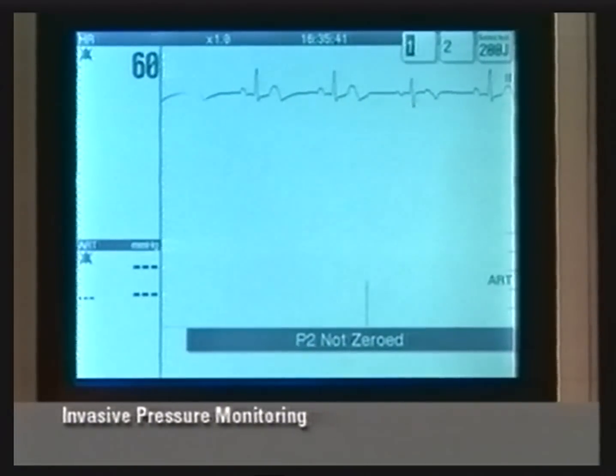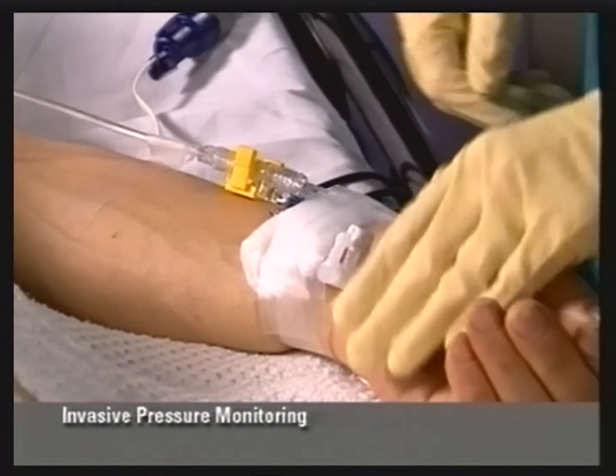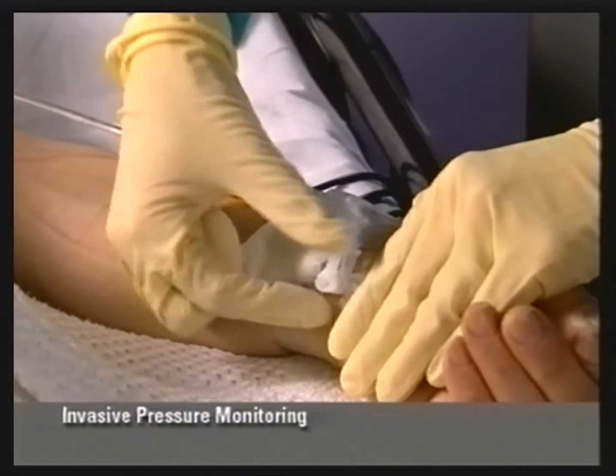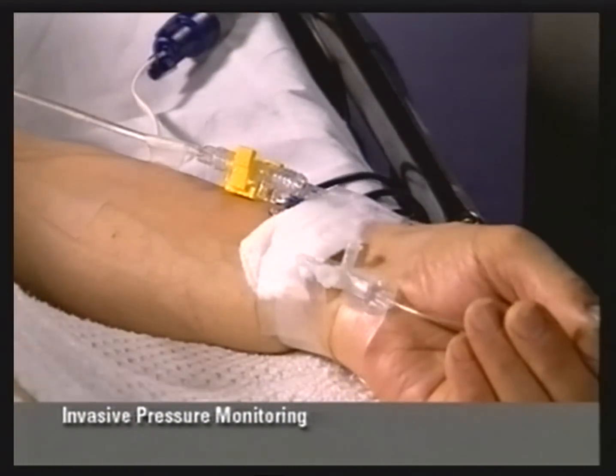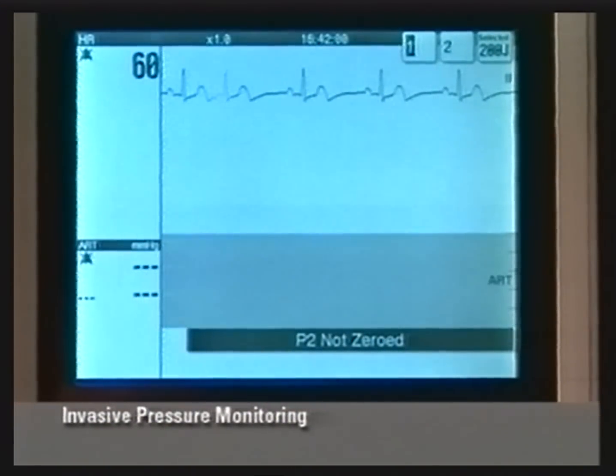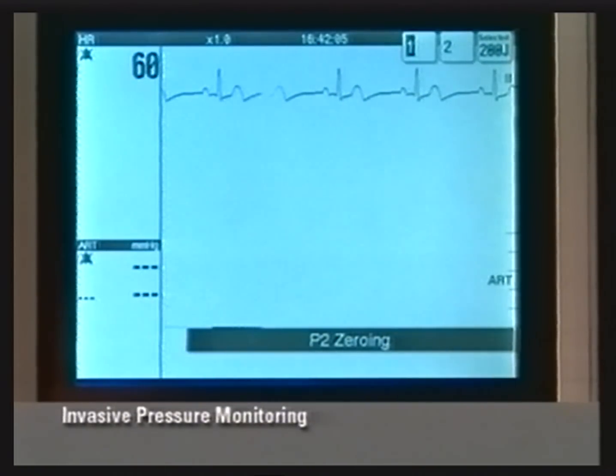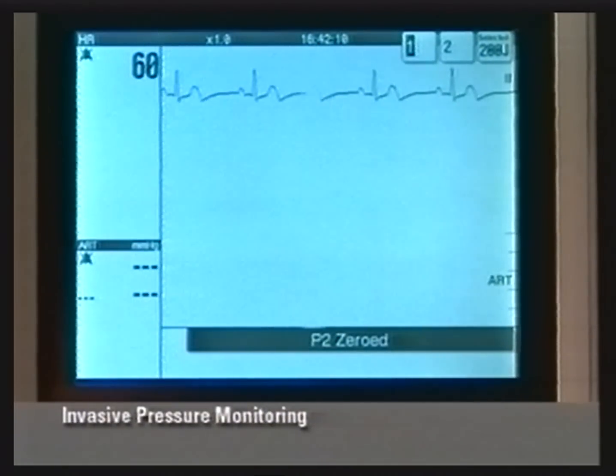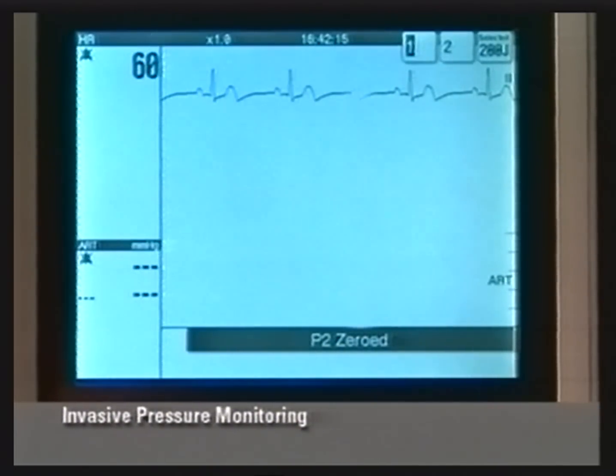Notice that the message P2 not zeroed is displayed in the status area. To avoid offset errors, a zero reference must be established before a meaningful pressure reading can be obtained. This is done by opening the transducer stopcock to air so that atmospheric pressure becomes the reference. Select 0 from the channel 3 or parameter menu. The messages P2 zeroing and P2 zeroed appear. When zeroing is complete, the pressure values are displayed as zeros.